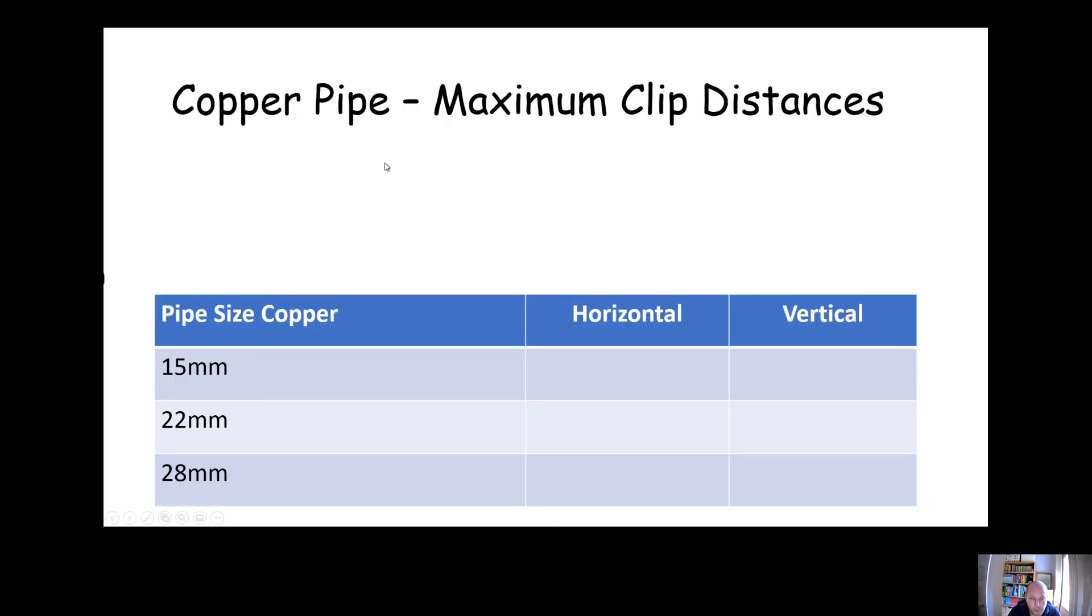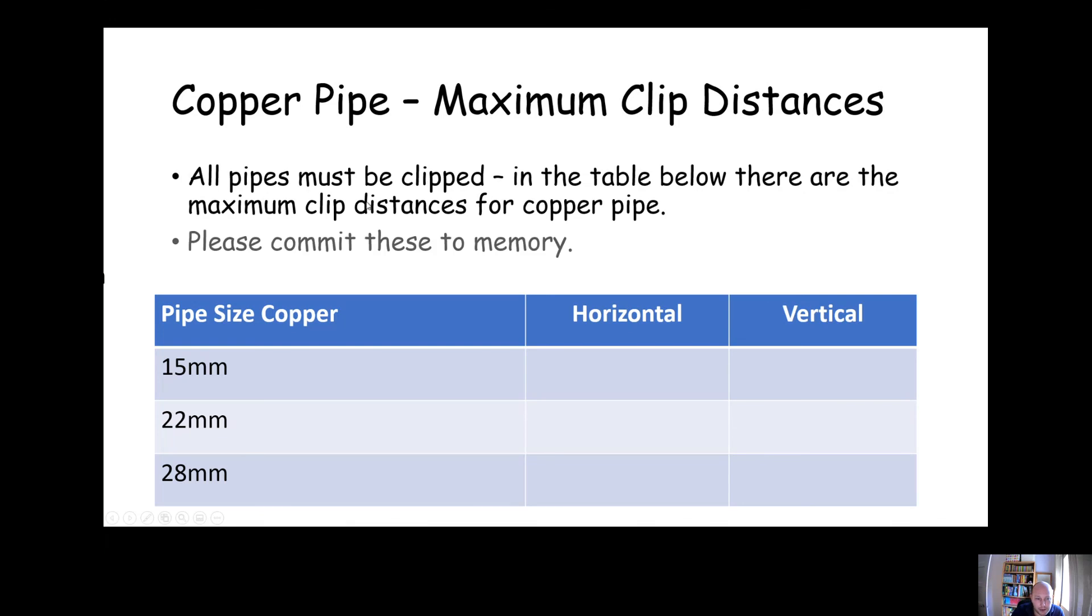One last thing: looking at pipe sizes, this is a key thing to remember. It will come up in several tests, so make sure we commit these to memory. For 15 mil copper, the horizontal maximum distance between two clips should be 1.2 meters, vertically 1.8. 22 mil and 28 mil are actually the same. 22 mil horizontally should be clipped every 1.8 at the absolute most, vertically 2.4. And 28 mil is just the same: 1.8, 2.4. Commit these to memory. It will be really worth your while.